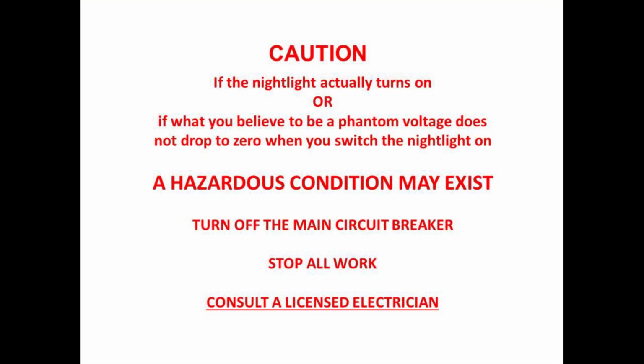Caution: if the nightlight actually lights up, or if the DVM reading does not drop to zero when you switch the nightlight on, the voltage is not phantom, and it's caused by a wiring fault. One of the faults that can cause this is a loose neutral on a multi-wire branch circuit. If you suspect this is the case, treat the measured voltage as being potentially hazardous. If you are at all unsure, consult with a licensed electrician.